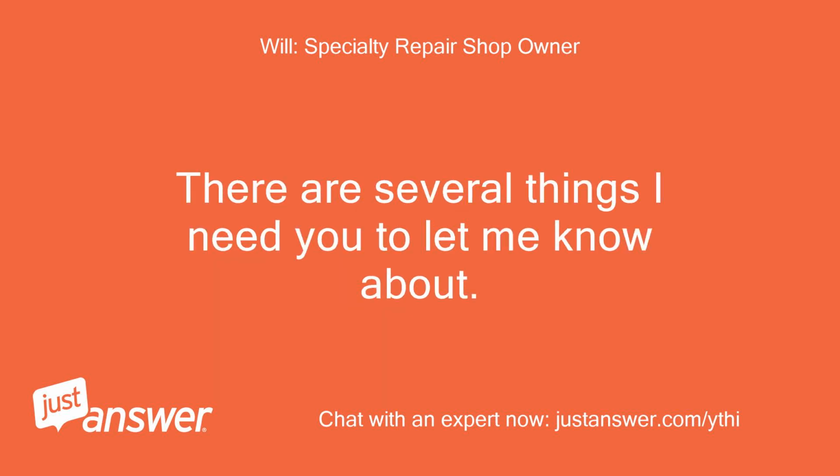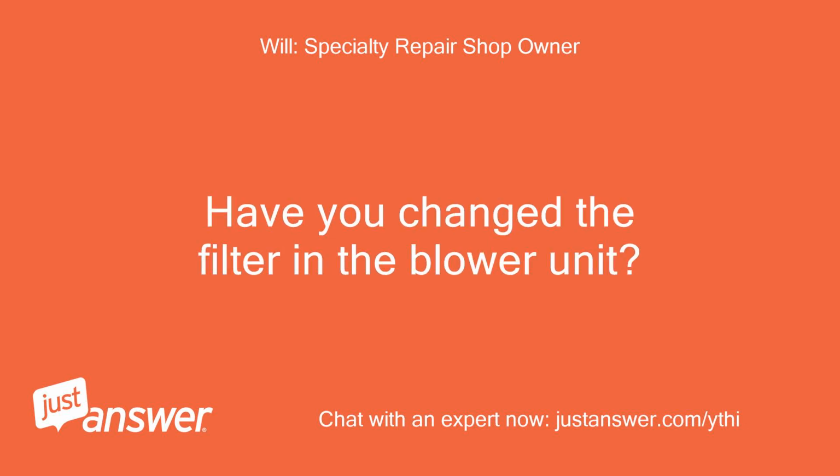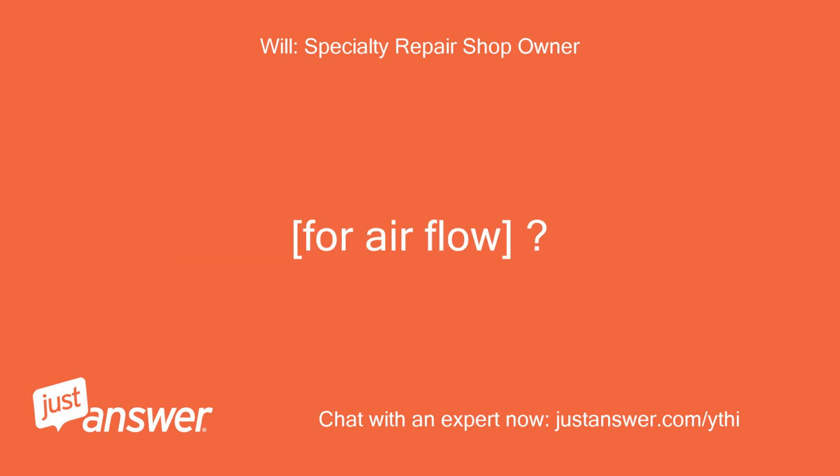There are several things I need you to let me know about. These may seem very simple and even insulting, but believe me, my best technicians will on rare occasion run a generator backwards and not notice it. Have you changed the filter in the blower unit? Or cleaned it correctly and completely? Both inside and outside filters. If it is a replaceable filter, is it pointing the right direction for airflow?